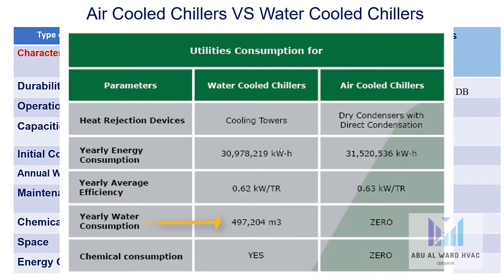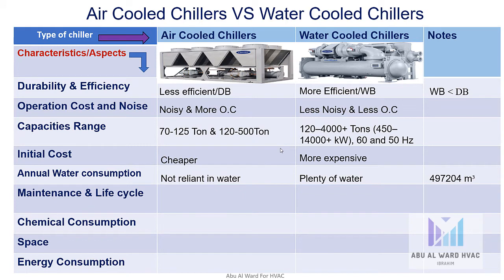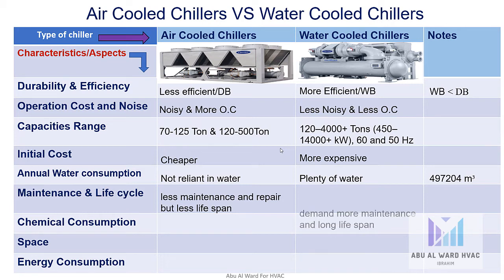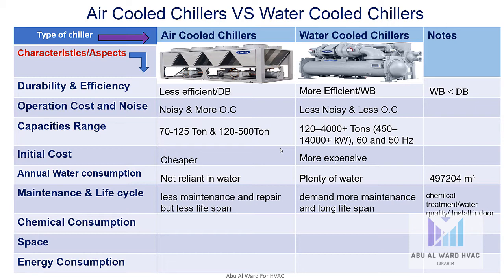According to this table, we can see the cooling tower requires about 497,000 cubic meters, while the air-cooled does not require water at all. The maintenance and life cycle. The air-cooled have less maintenance and repair, but the life cycle span is less, while the water-cooled demand more maintenance and have a long lifespan because of chemical treatment requirement, water quality, and it can be installed indoor. That's why the lifespan is more. The chemical consumption for air-cooled is zero, and there is chemical consumption for water-cooled chillers.